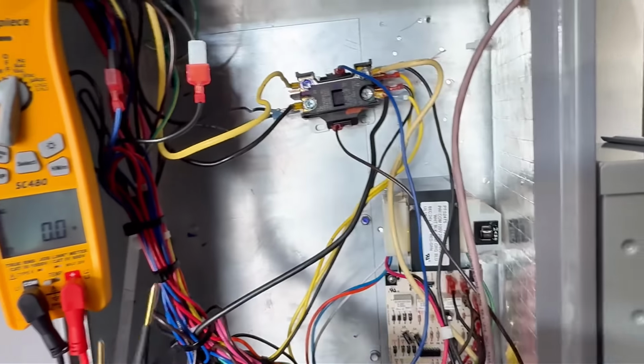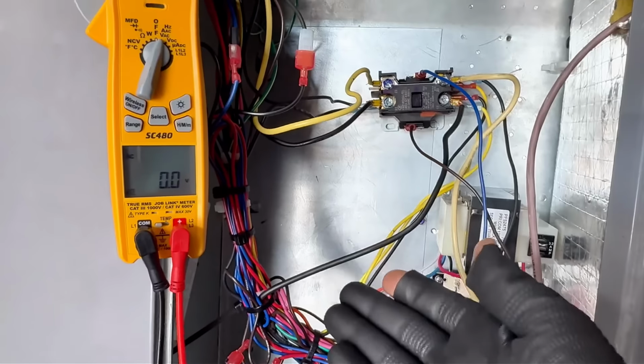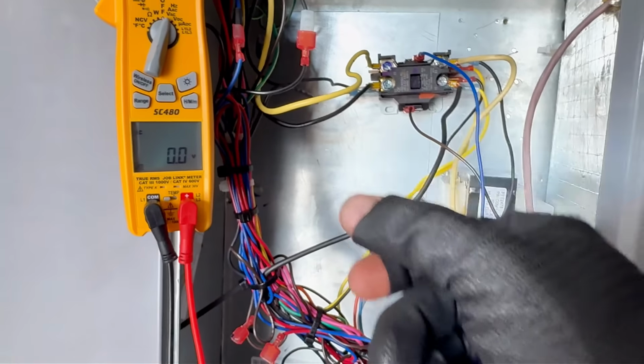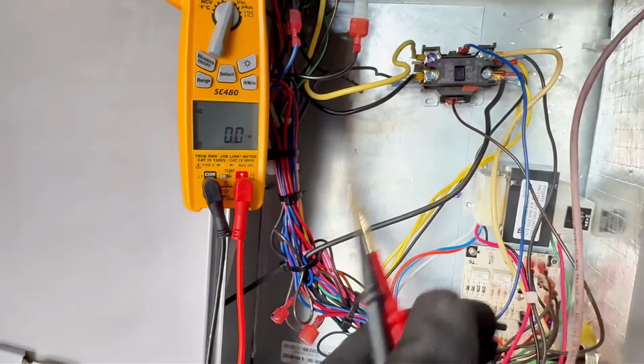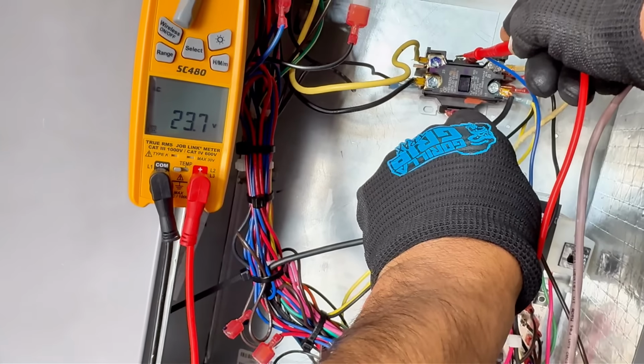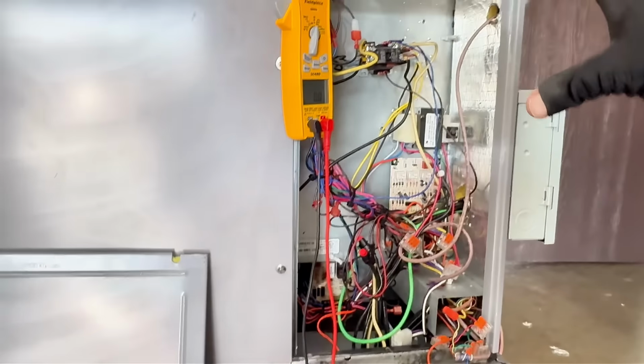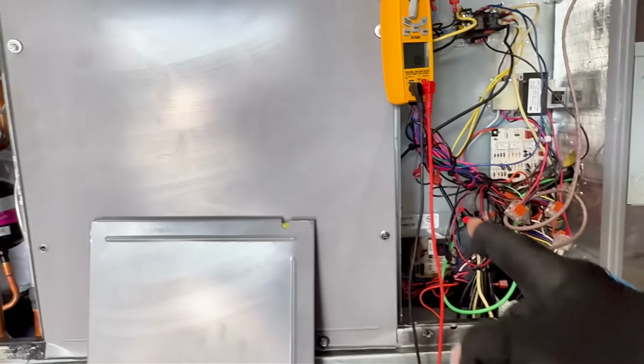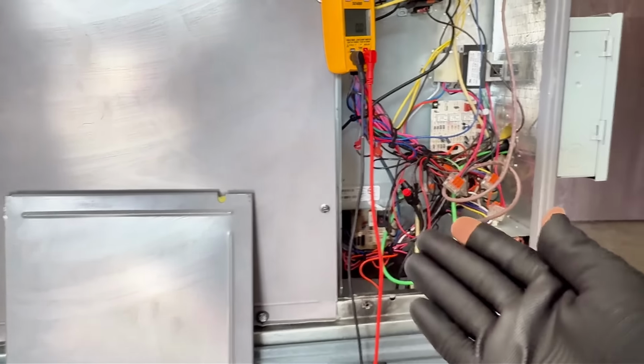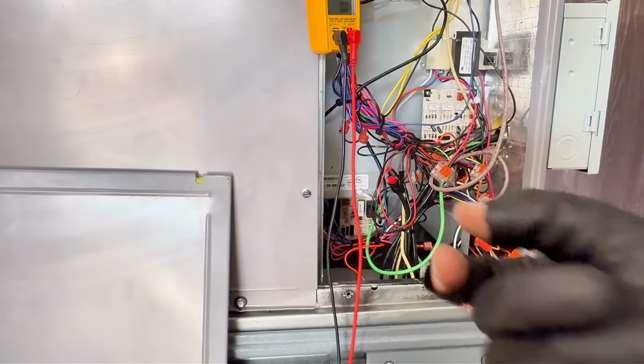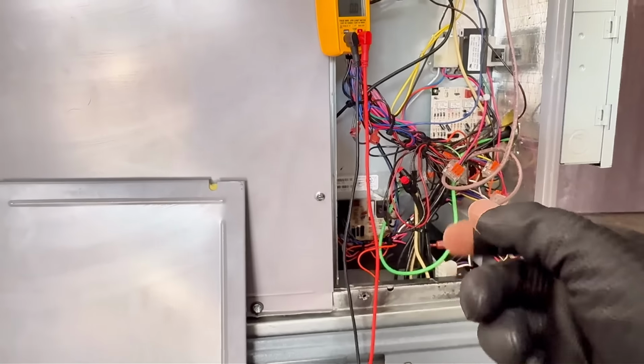Interesting. So that could happen because when you're trying to put everything back, and then they call you back saying, hey, it's not working. All it was is that little Molex plug was put on the wrong place, and that has happened so many times. I've gotten a couple callbacks like that, but you see I'm getting 24 volts and it's on. Good. Okay, so that was the issue. Thermostat was good, the wire was good, the 24 volts going that way, it was just right there. There was a little delay because I did unplug it, kind of reset the delay a little bit, but once I connected it back, it turned on, compressor turned on. So the Molex connector was plugged incorrectly.